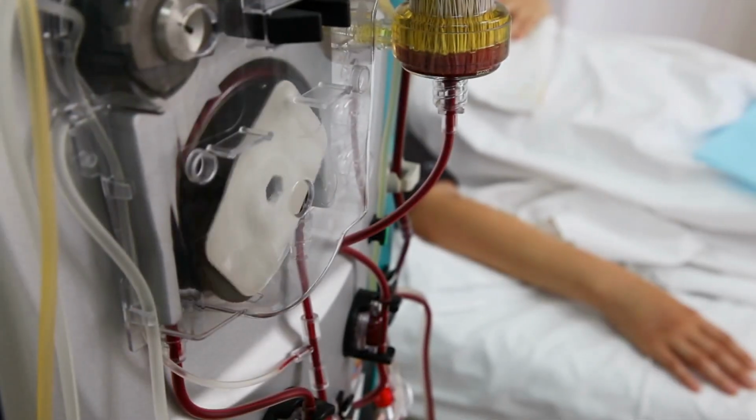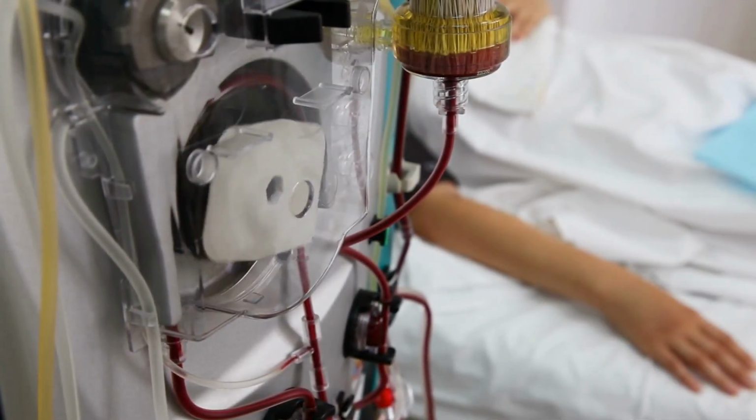Next, let us talk about indirect contact pathways, which add a layer of complexity. Devices like blood storage bags, dialysis tubing, or infusion systems may not touch the body directly but can transfer substances into the body. In these cases, ISO 10993-1 requires a thorough evaluation of all possible biological risks. For example, dialysis tubing may leach chemicals into the blood during use, and those leachables must be tested for cytotoxicity, sensitization, and systemic toxicity.